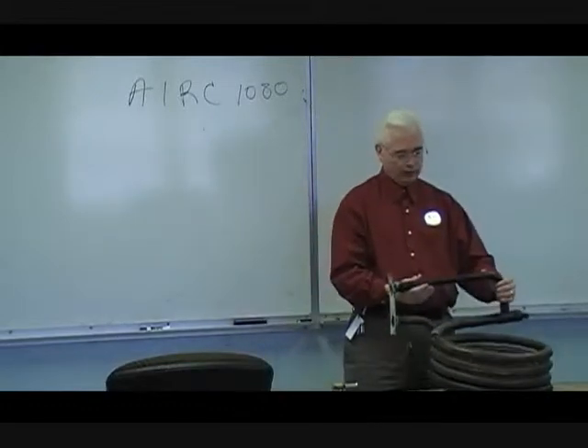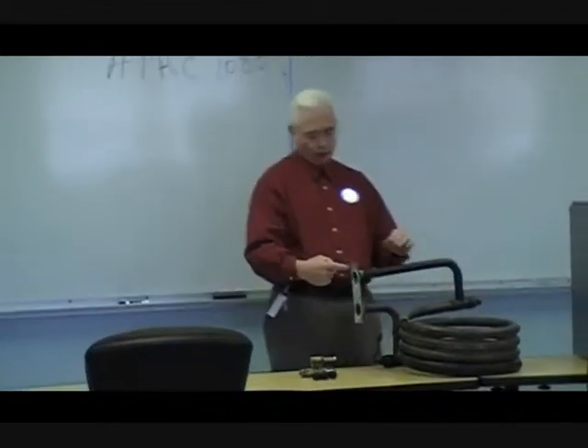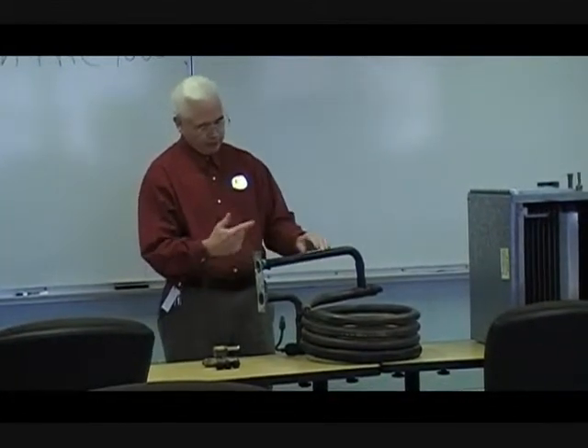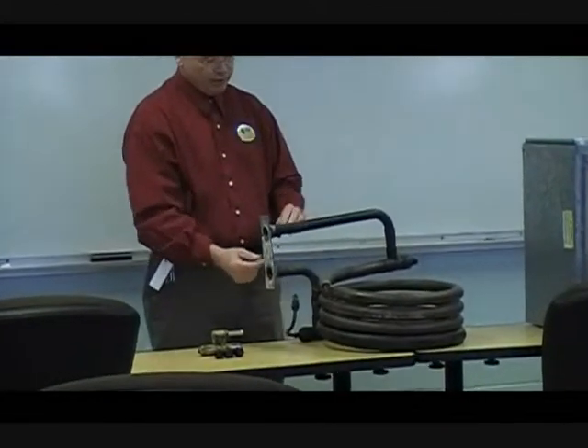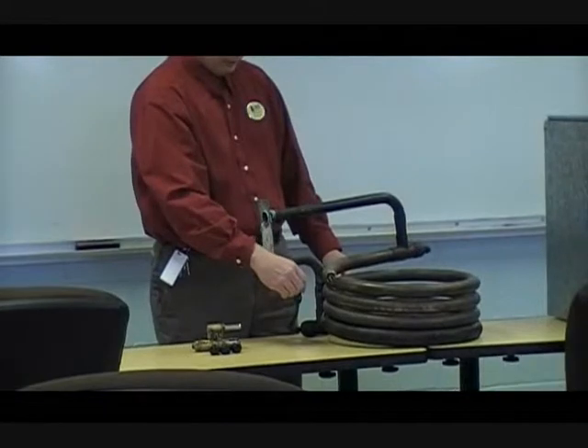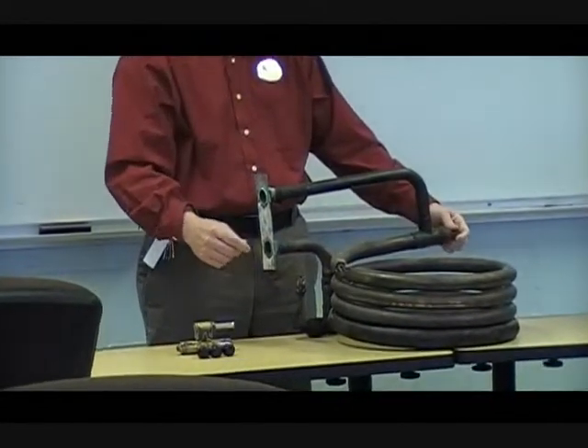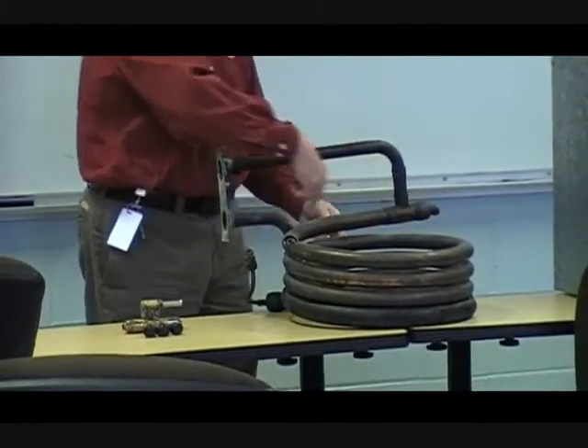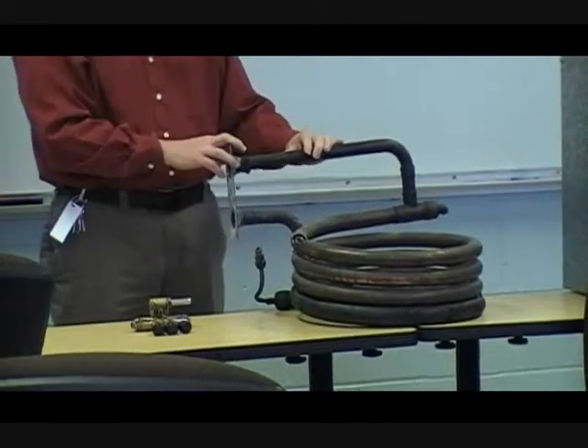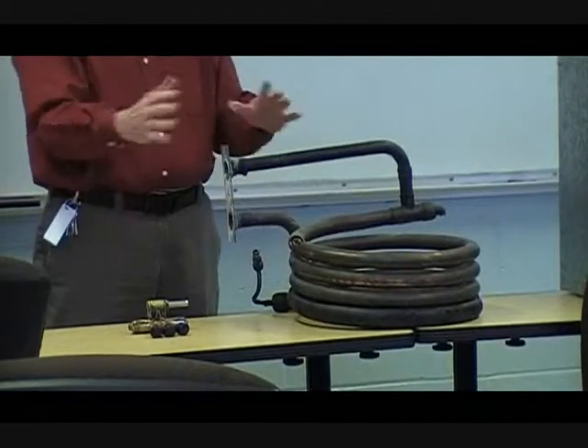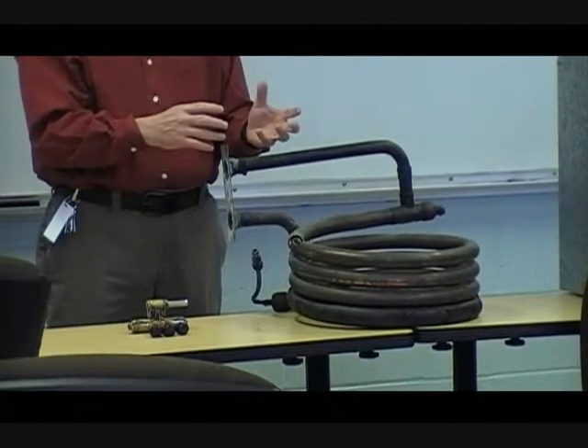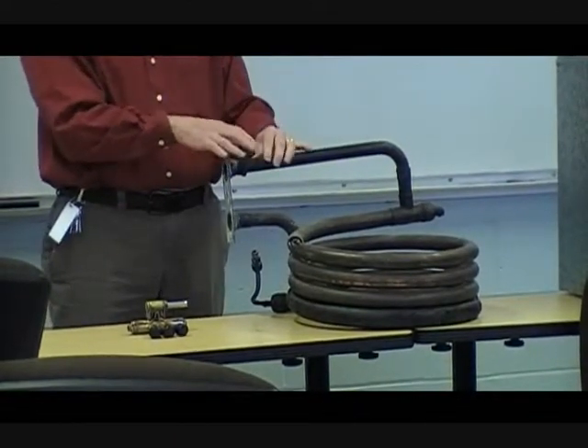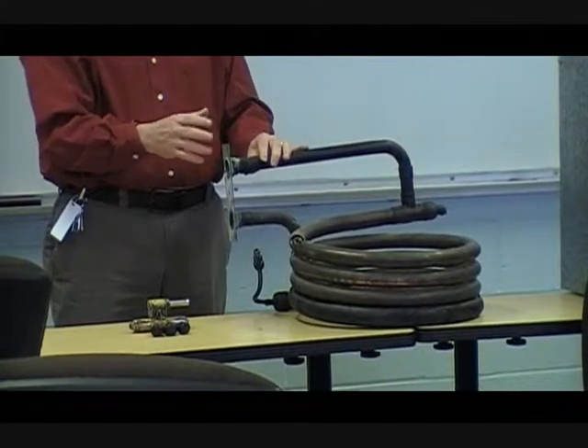This is an example of a water coil. The water would enter here — you've got an inlet and an outlet. The water comes in, circulates through the coil, and comes out. These are refrigerant lines; the refrigerant comes in here and it leaves here. You've got the refrigerant tubes that are actually encased inside the water tube. This is a water coil, and it's using water as a medium of exchange for the refrigerant to either give up heat or absorb heat inside the coil. That's basically the difference between the air coil and the water coil.